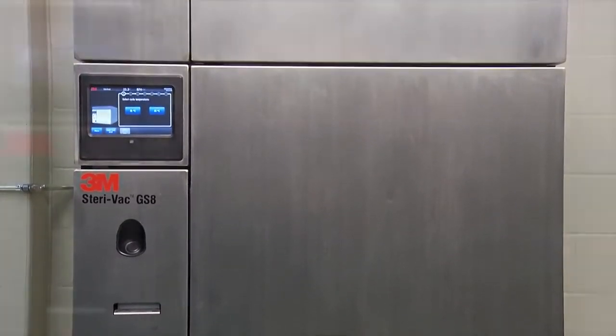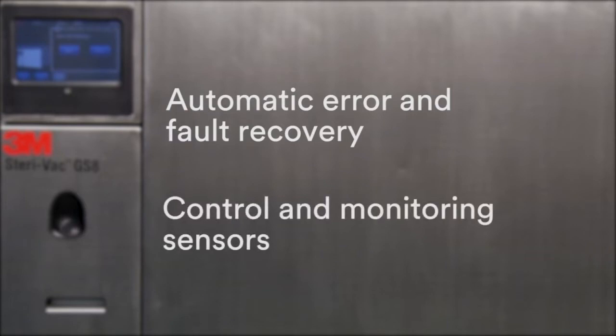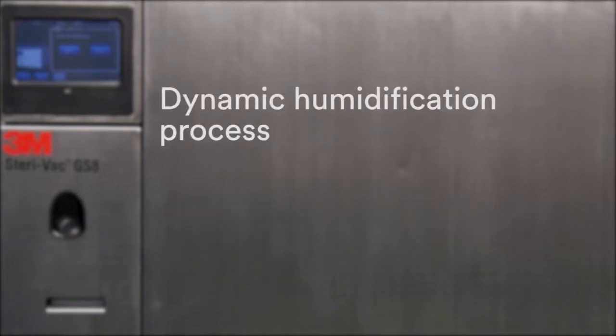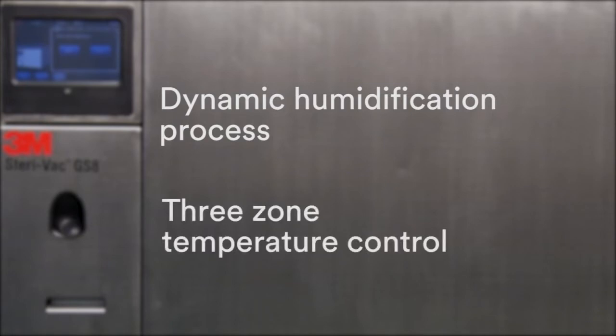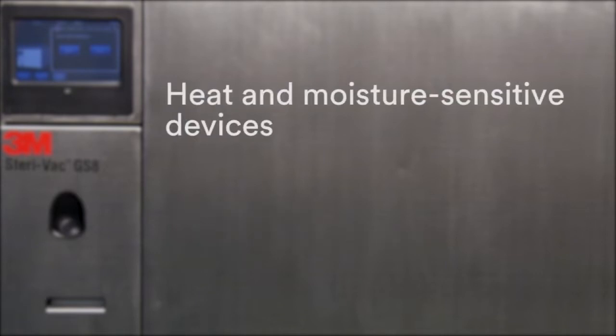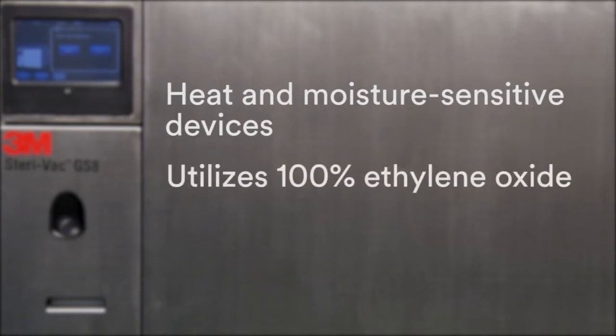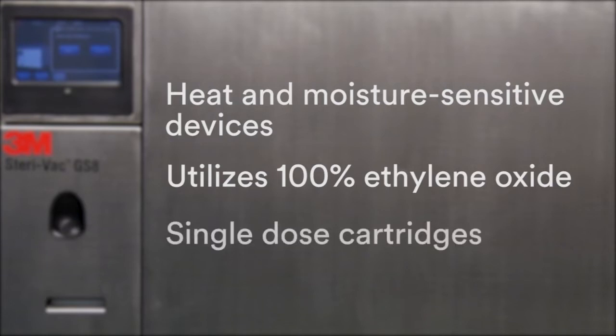Those features include an automatic error and fault recovery, control and monitoring sensors for pressure, percent relative humidity, and temperature parameters, a dynamic humidification process with measurement and feedback control, and a 3-zone temperature control to improve temperature uniformity. This low-temperature sterilizer is used to sterilize heat and moisture-sensitive devices and utilizes 100% ethylene oxide as the sterilant. The sterilant is delivered via single-dose cartridges.